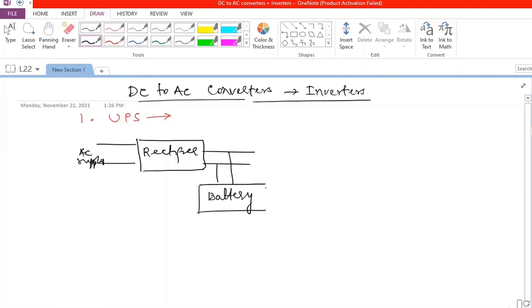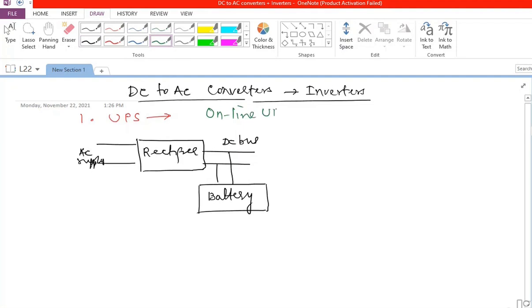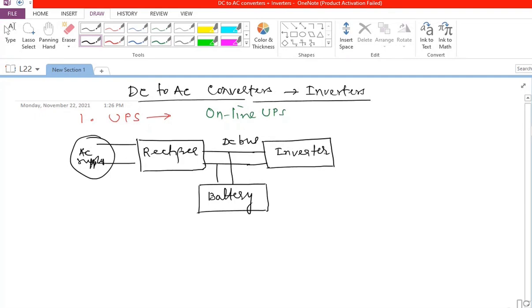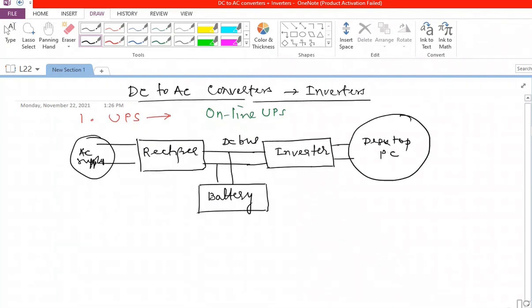The battery stores power in case of a power supply failure and can provide power to the DC bus. In an online UPS, right after the DC bus there is an inverter, so the DC supply is converted into AC. Even if there is any fluctuation on the AC supply side, it will not affect the computer getting power from the inverter.